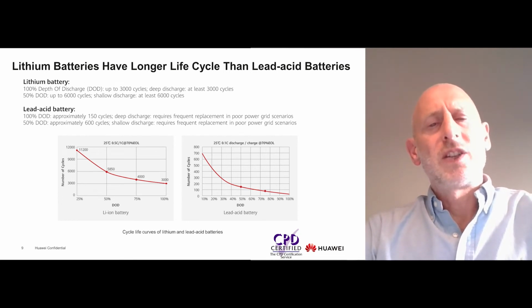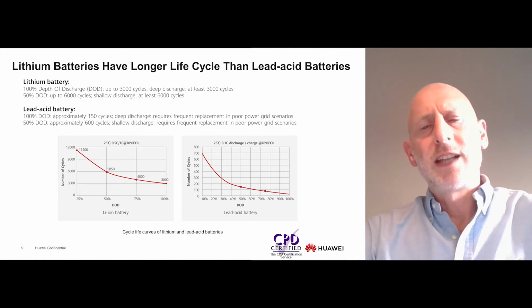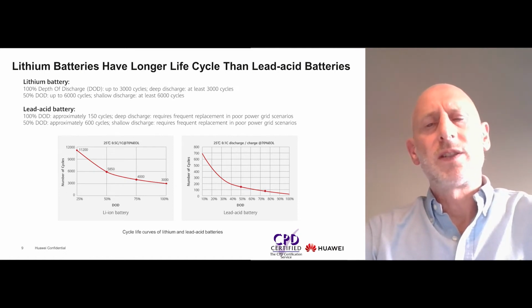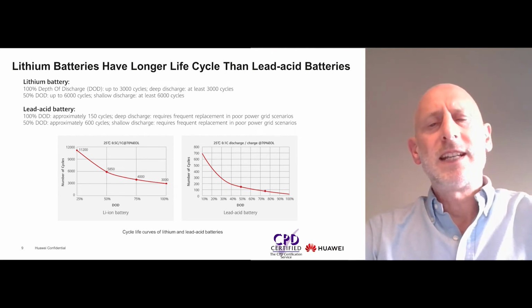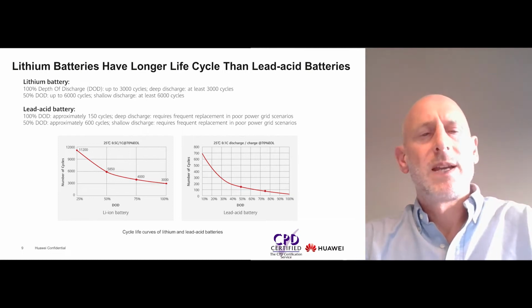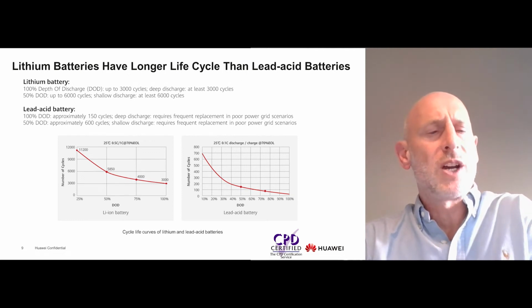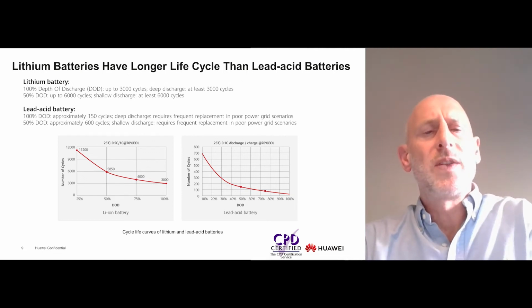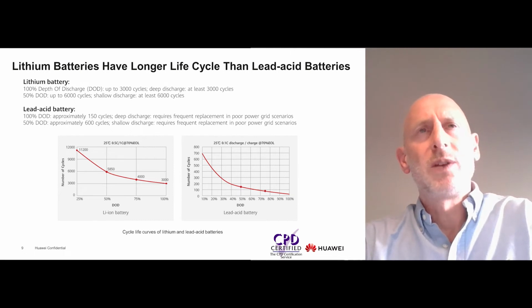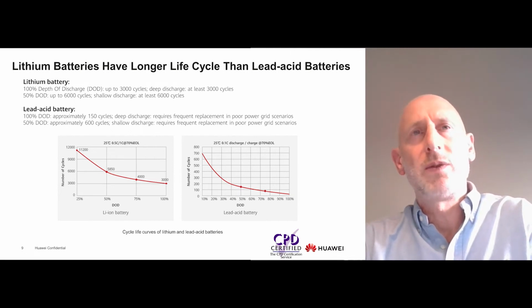Lithium-ion batteries can achieve up to 6,000 cycles, much longer than the 600 cycles of lead-acid batteries. Therefore they can be implemented in data centers for longer and don't require costly replacements as often. The key takeaway is that lithium-ion batteries have impressive longevity with over 6,000 recharge cycles, 10 times more than lead-acid batteries, which will dramatically affect total cost of ownership.